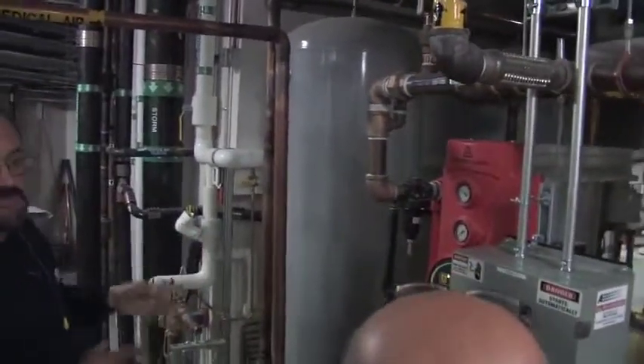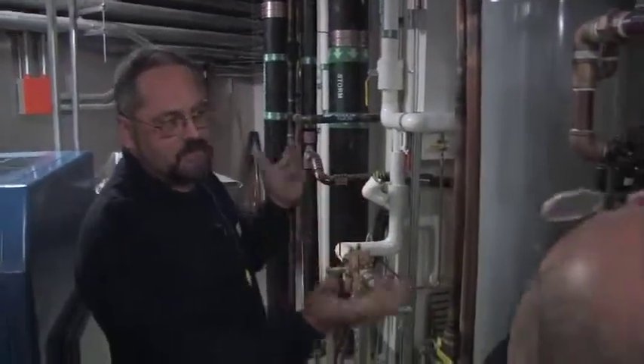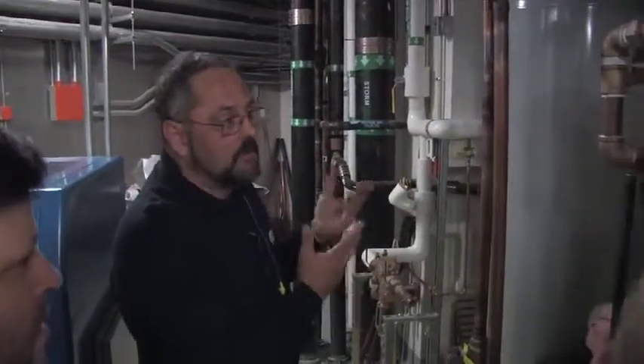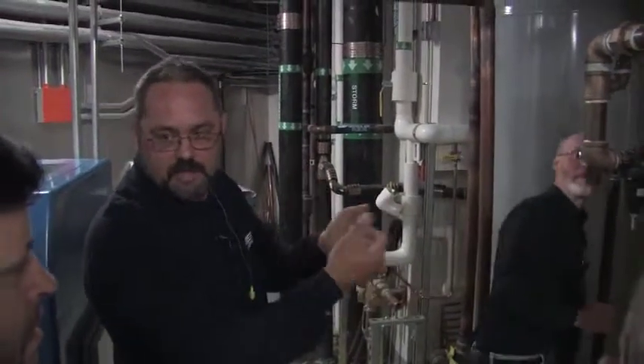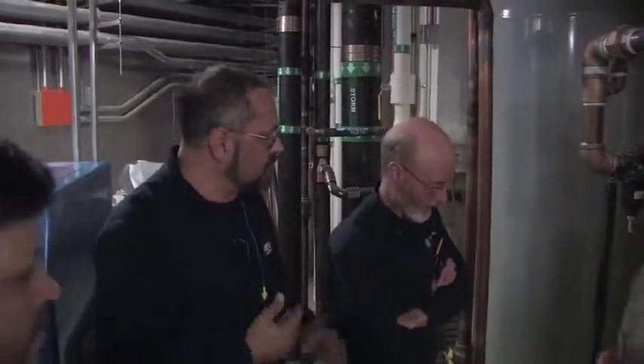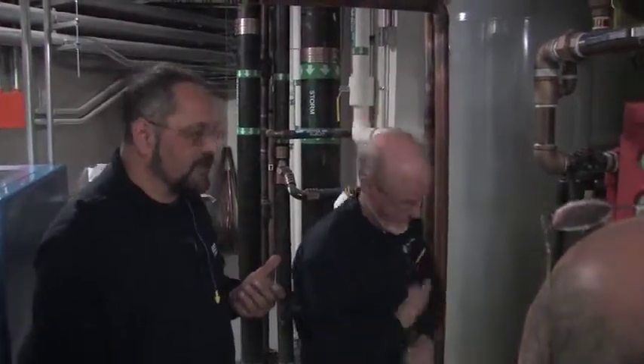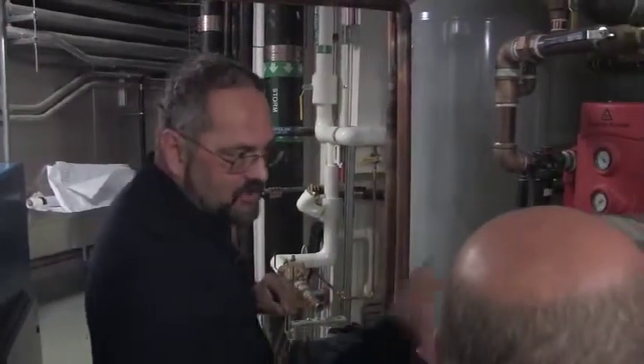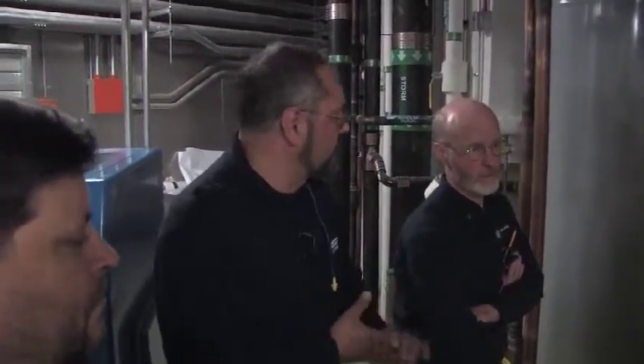The maintenance on these is every 6 months or once a year if you're alternating the dryers. You want to change that inlet filter and the outlet filter, and you want to replace the muffler. That's basic annual maintenance. Oh, you do want to replace the muffler every time? You should replace the muffler because the muffler is also getting dusted from the beads. So eventually the muffler will build up enough dust that your gauge here, instead of reading 0, might read 2 or 3 pounds. The higher that pressure, the higher that back pressure, the less efficient the purge is going. So rule of thumb is change the mufflers too.